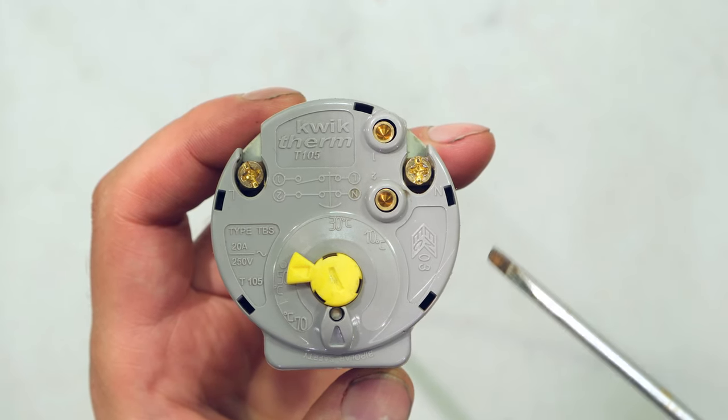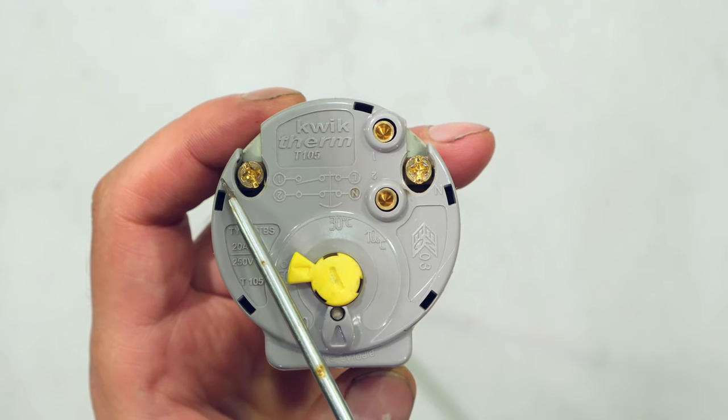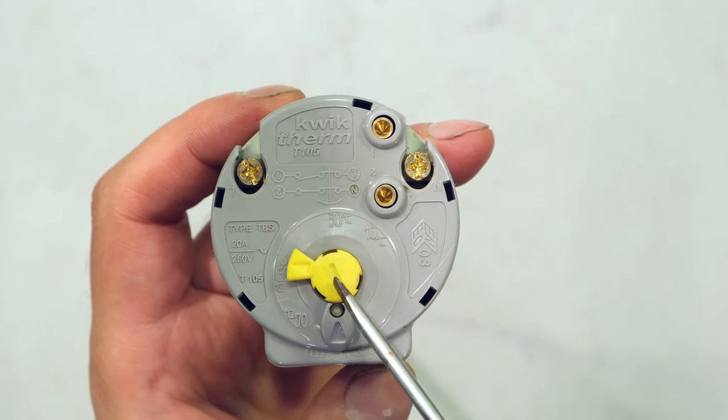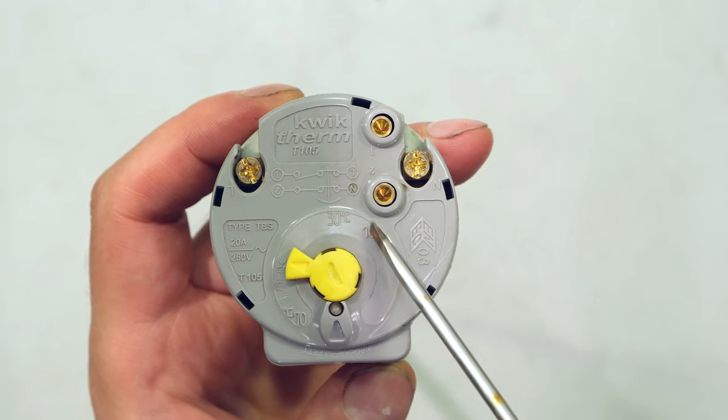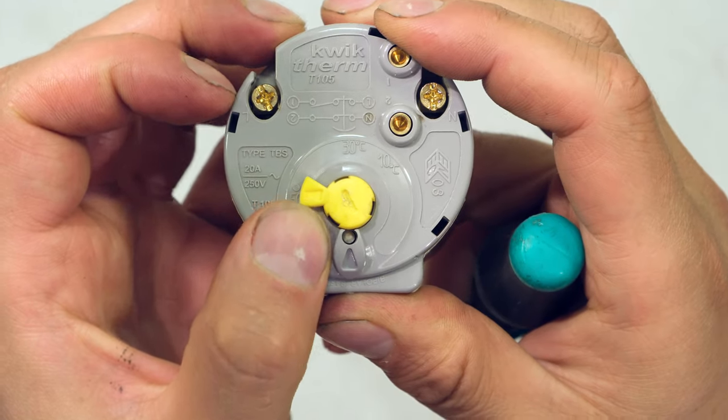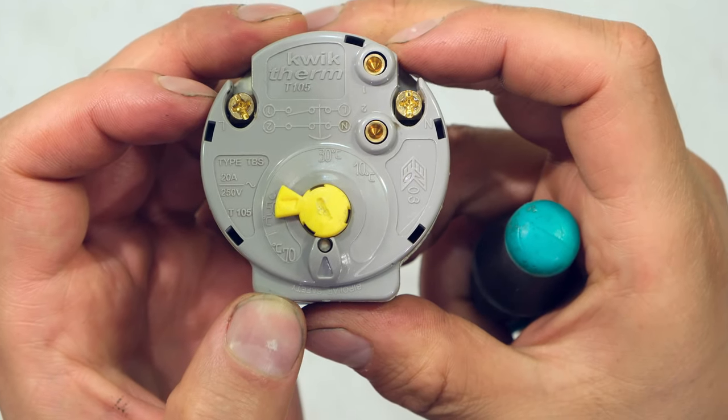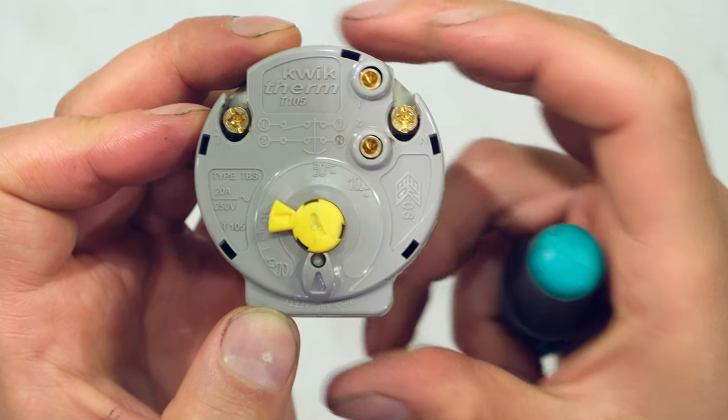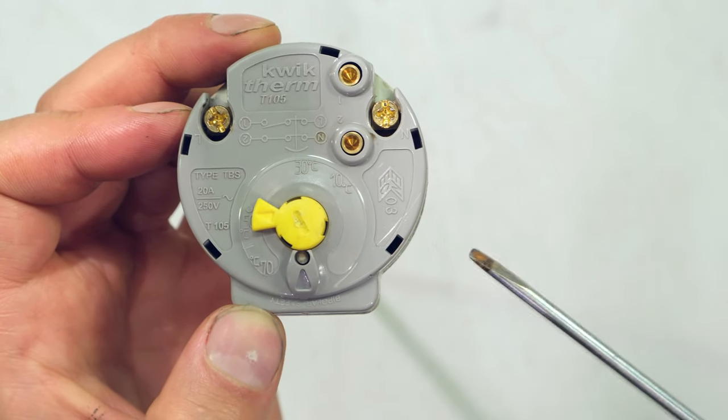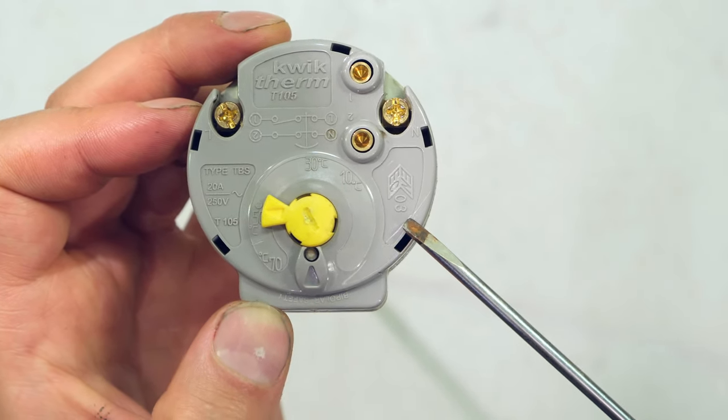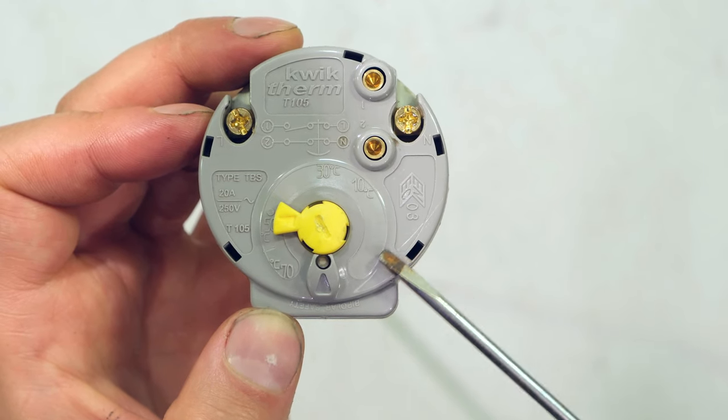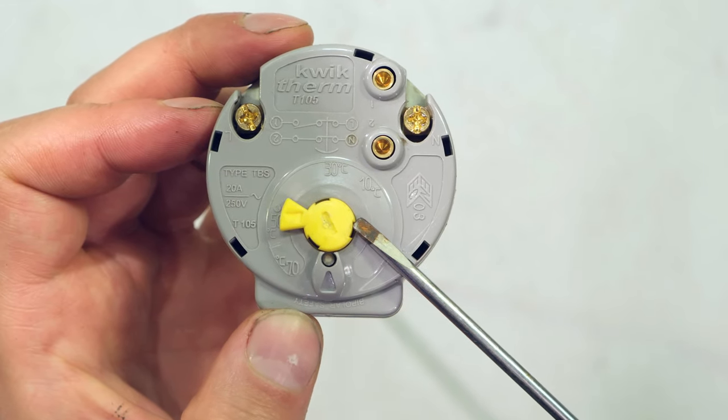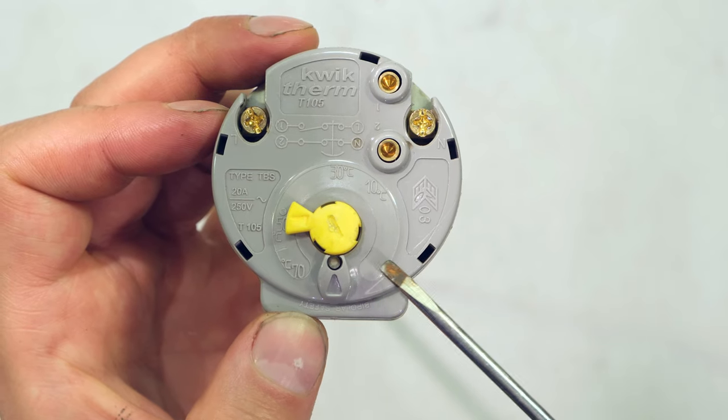Right over here I have the face of the thermostat. There is the neutral and on this side is the live. And over here I've got the temperature selector - this is in degrees centigrade. So if I move this to there, I've now set the thermostat to 50 degrees. That means that the thermostat must remain in a closed position until the water temperature reaches about 50 degrees. It's not exact because of hysteresis, but that's a whole other video.